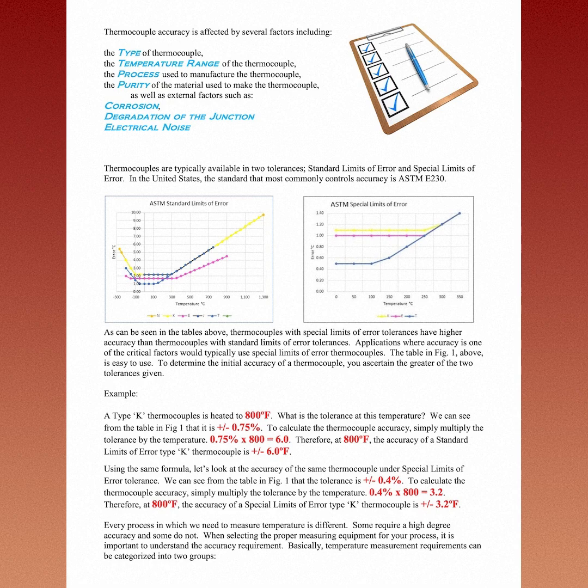To determine the initial accuracy of a thermocouple, you ascertain the greater of the two tolerances given. Example: a type K thermocouple is heated to 800 degrees Fahrenheit. What is the tolerance at this temperature? We can see from the table in Figure 1 that it is plus or minus 0.75%. To calculate the thermocouple accuracy, simply multiply the tolerance by the temperature. 0.75% times 800 equals 6.0. Therefore, at 800 degrees Fahrenheit, the accuracy of a standard limits of error type K thermocouple is plus or minus 6.0 degrees Fahrenheit.